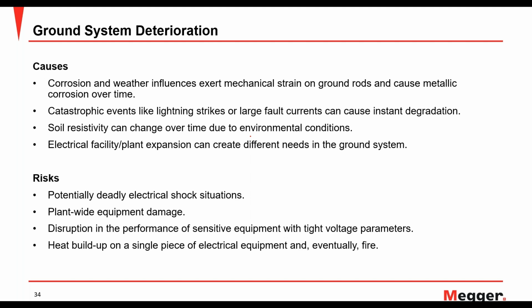Usually, when a lightning strike occurs, your grounding system is good. It survived that lightning charge, but it also took a lot of strain on the grounding system itself. So next time it might not be as accurate, and after 2, 3 instances like that, the grounding system might even fail, and that's when you would have a potential risk of failure of the whole system.